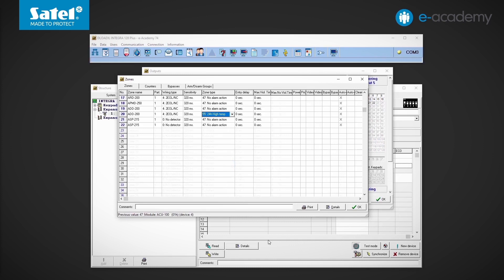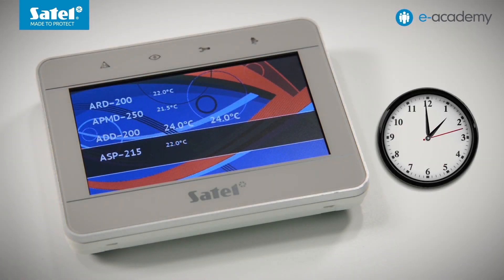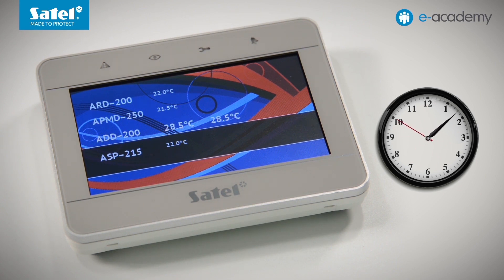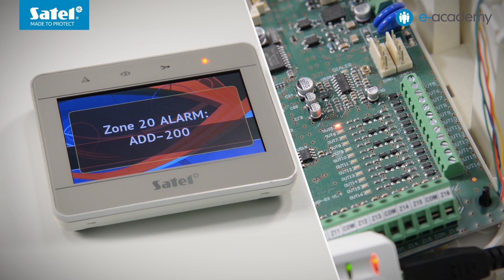We go to the controller settings and in the zones outputs table next to the temperature detector, we change the threshold to the high threshold. The temperature is set to 30 degrees Celsius. We write the data to the controller and also save the data to the control panel. The service mode has been deactivated. The detector has been placed next to the heater. We can see the temperature rising, and when the set threshold temperature is exceeded, an alarm is triggered.